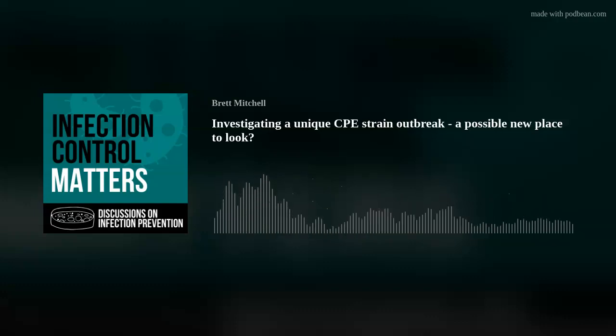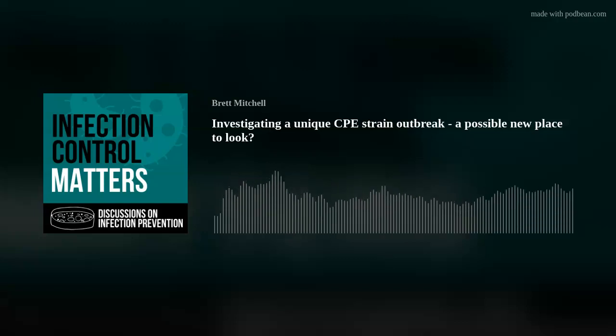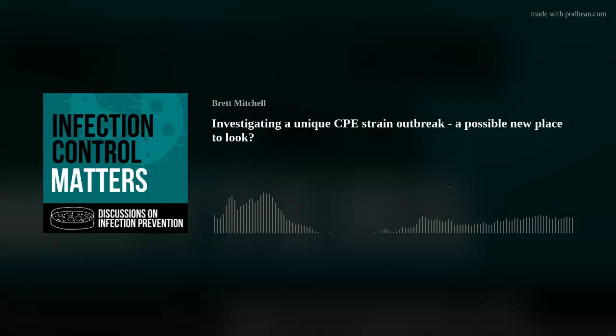What we also did find is around traceability, that we found some being used in clinical areas and then being moved to other areas. So the one that was used in the food processing unit probably had been used at some point in a clinical area as well. So what have you done about it now? Have you said we've got to put these into specific areas and they stay within that area, or have you gone down the different decontamination routes? The ones that were contaminated, we ultimately condemned because we couldn't decontaminate them in any way. What we've tried to do is rationalise where they're used, avoiding as much as possible their being used in clinical areas.